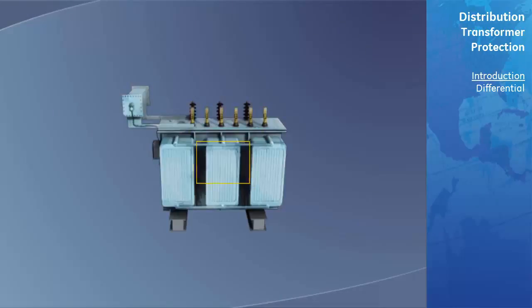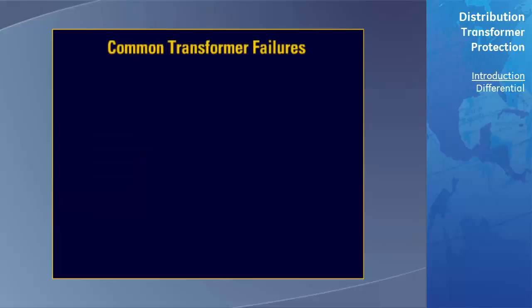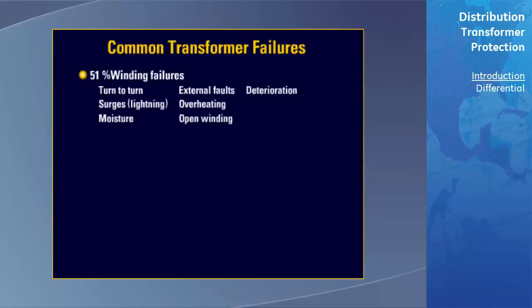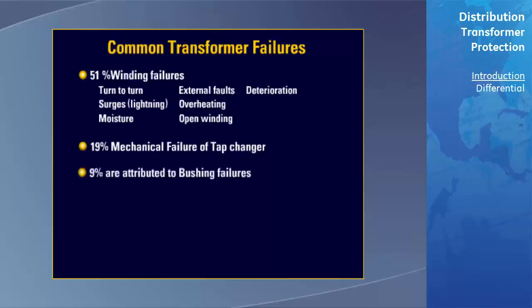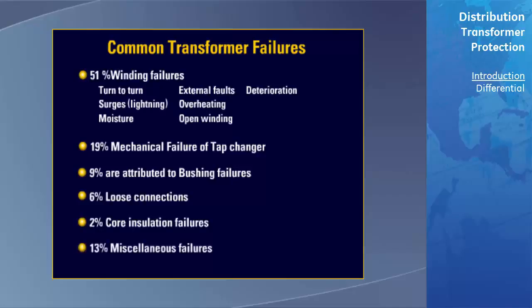A study performed on transformer failures found the following information. 51% were classified as winding failures, which include turn-to-turn failures, surges due to lightning, moisture, external faults, overheating, open winding, or deterioration. 19% were related to a mechanical failure of the tap changer. 9% were attributed to bushing failures due to aging, contamination, or cracking. 6% can be traced to loose connections on the terminal board. 2% were due to core insulation failures. And the remaining 13% were simply classified as miscellaneous failures.